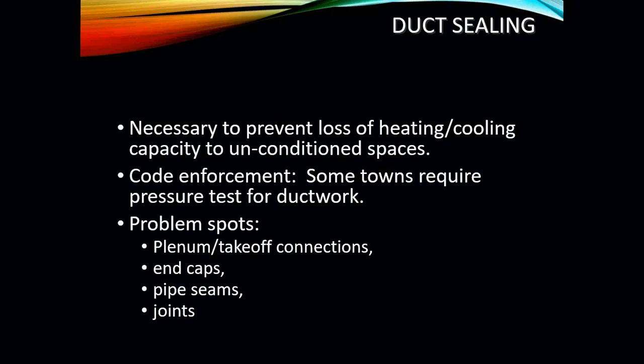When it comes to duct sealing, it's very important to prevent the loss of heating and cooling capacity to unconditioned spaces. We don't care about areas that won't be conditioned. We want full capacity of heating and cooling in our ductwork, delivering it to the spaces where we want it to go. So in order to do that, we have to duct seal.